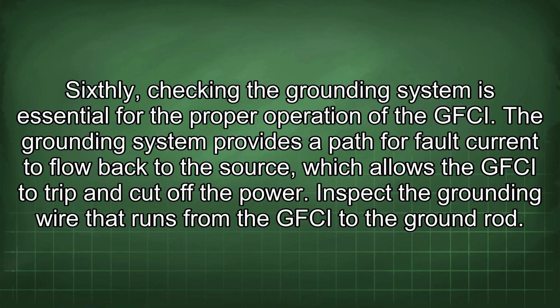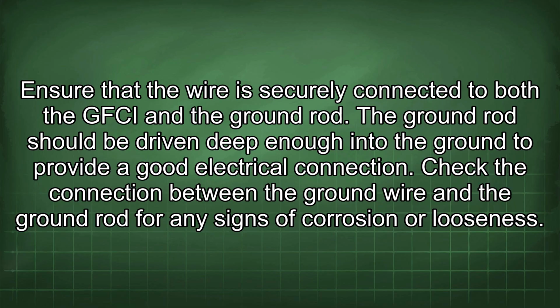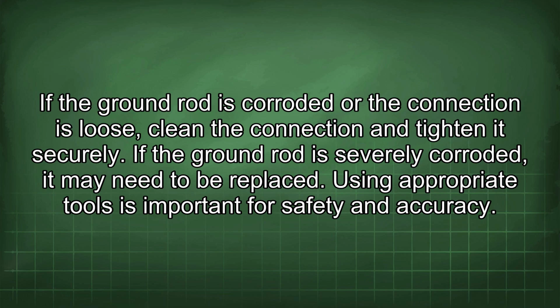Inspect the grounding wire that runs from the GFCI to the ground rod. Ensure that the wire is securely connected to both the GFCI and the ground rod. The ground rod should be driven deep enough into the ground to provide a good electrical connection. Check the connection between the ground wire and the ground rod for any signs of corrosion or looseness. If the ground rod is corroded or the connection is loose, clean the connection and tighten it securely. If the ground rod is severely corroded, it may need to be replaced.